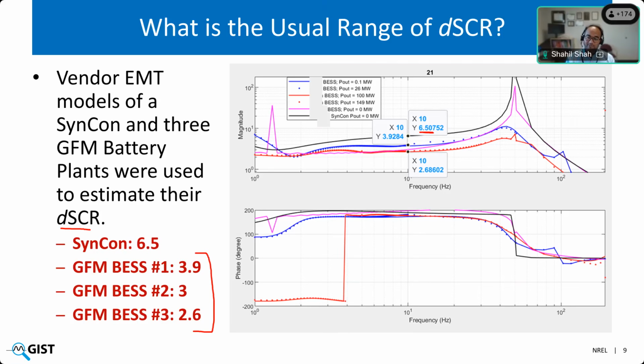As long as you are operating within the same control mode, the Q by V gain is going to be the same. But that again doesn't mean that you are getting the same grid strength. For small signal stability, yes, you are getting the same grid strength. But for large signal transients, like some bigger disturbance, if you're operating the BESS at full power and there is a disturbance, the BESS might saturate, and its grid strength during that period will suddenly go down. This gain will go down. That's why we have to be careful on how we use the small signal characteristics for sizing large signal response. But the gain really, we haven't seen it changing with the operating point.